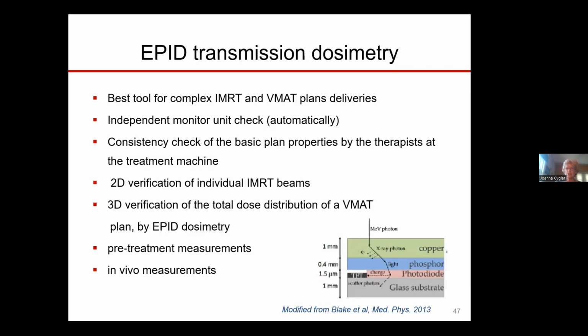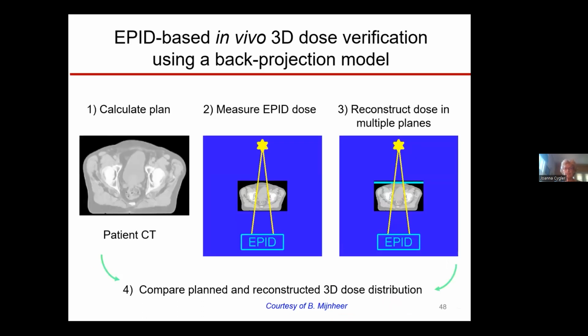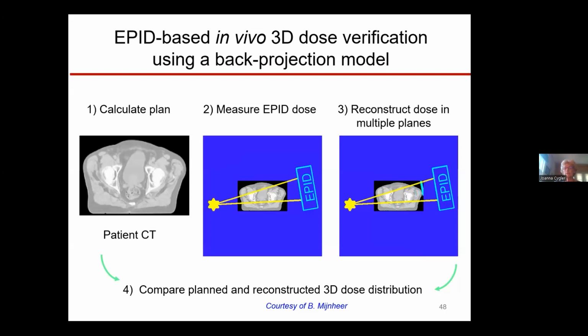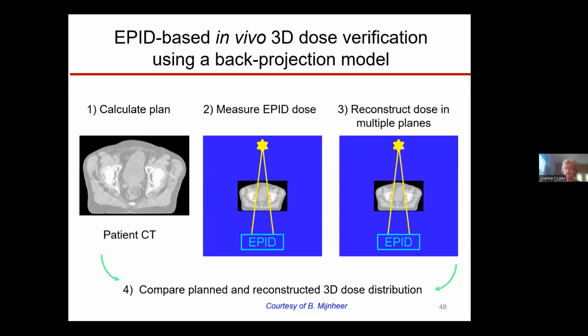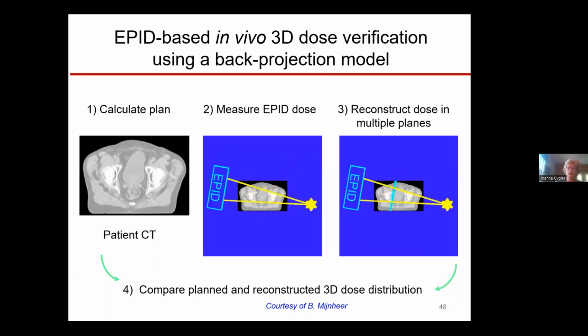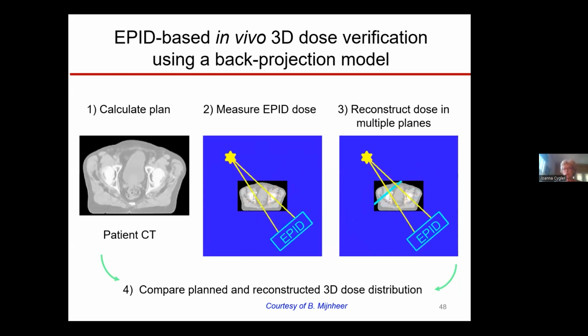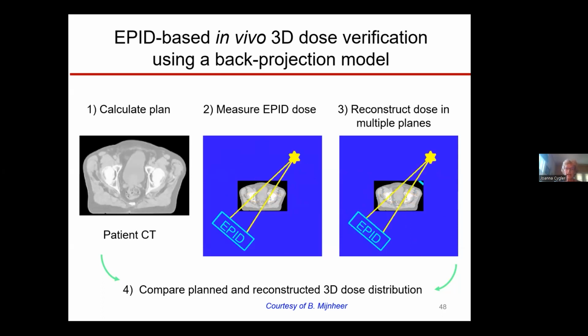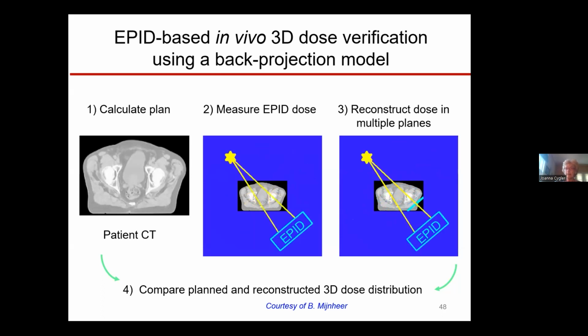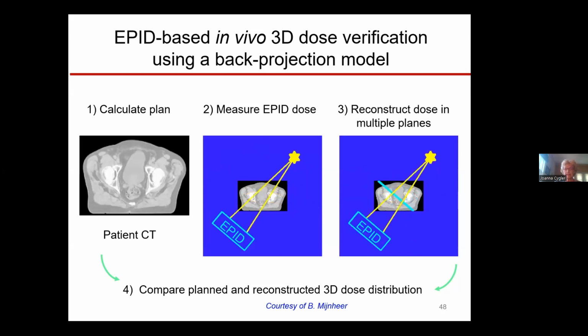And especially with the introduction of the amorphous silicon devices, shown here schematically in the right corner, the interest in EPID-based dosimetry has been accelerated, because amorphous silicon allows for fast dose acquisition, high resolution digital format, and reconstruction of the in vivo measurements and 3D dose verification. And the leader in this development has been the National Cancer Institute in the Netherlands. And they developed new software and clinically introduced it to allow automated image acquisition, periodically inspect the record and verify database, and automatically run the dosimetry software.